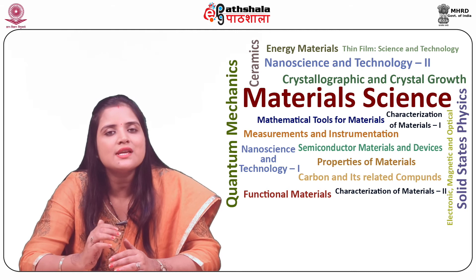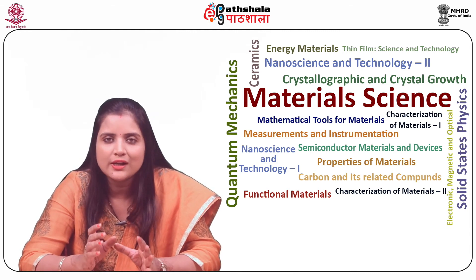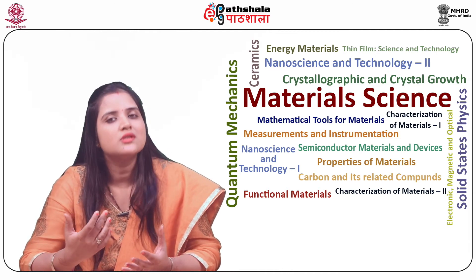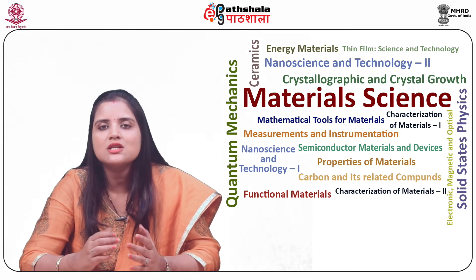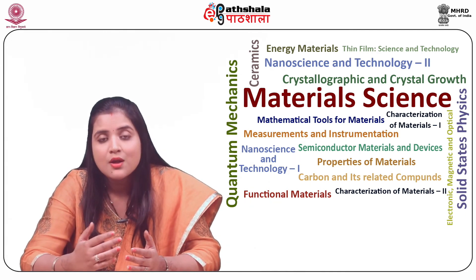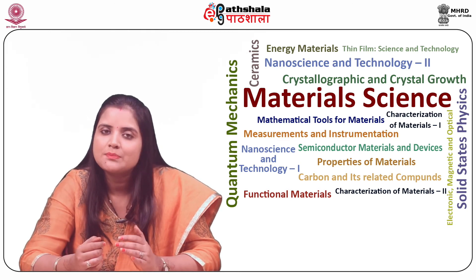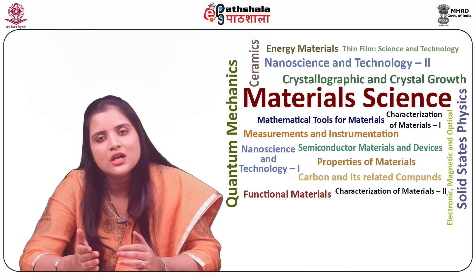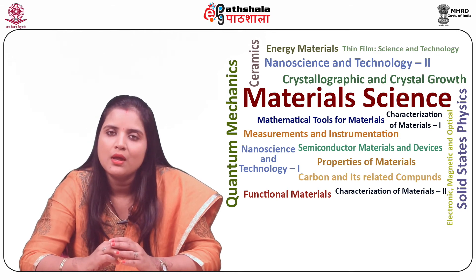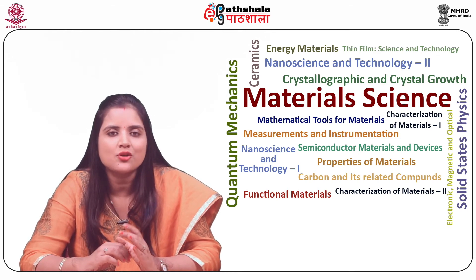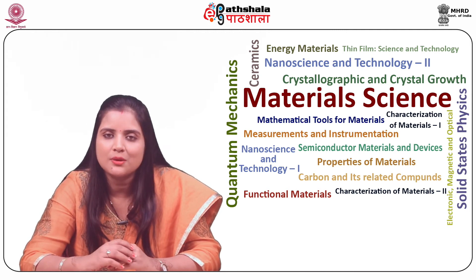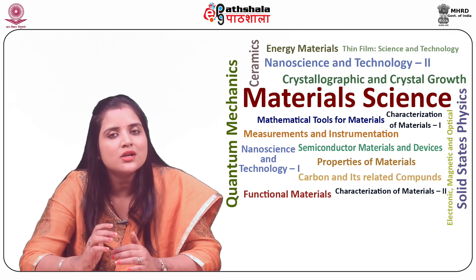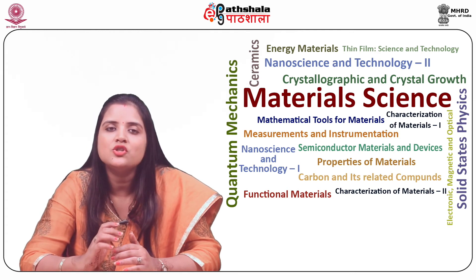Now we will discuss about gratings. Reflection grating is the crucial part of a monochromator whose purpose is to disperse incident light through rules which are positioned vertically. Spectra are acquired by grating rotation; the gratings contain 1200 grooves per mm and are blazed at 330 nm excitation and 500 nm emission. To overcome oxidation of the grating, it is coated with a protective layer of MgF2.